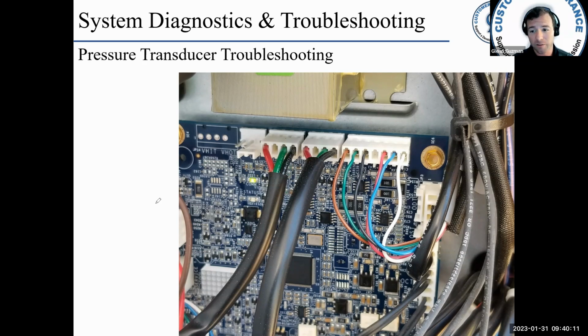It doesn't matter if they're actually connected to suction or discharge, that's what the board is going to assign. Okay, and it assigns it based on what the pressure is. It makes sense. If it's 100 PSIG and the other transducer is 300, well, yeah, the 100 must be suction, right? Well, it may or may not be. Okay, so that's where we as technicians come in and we have to really try to identify what is what here.